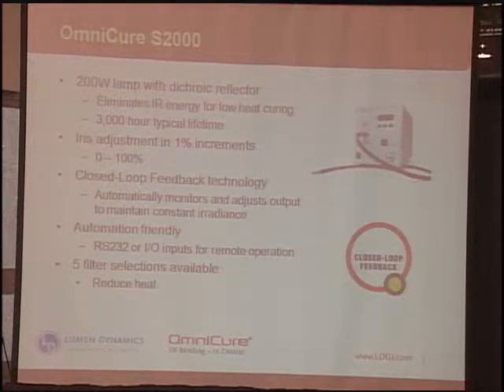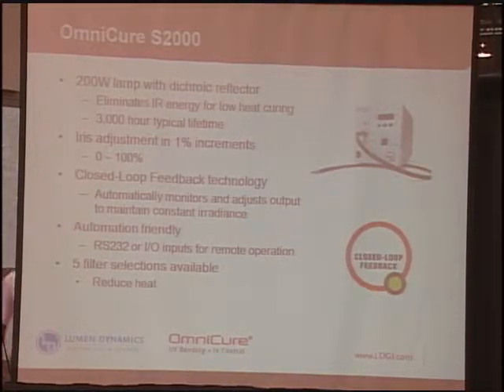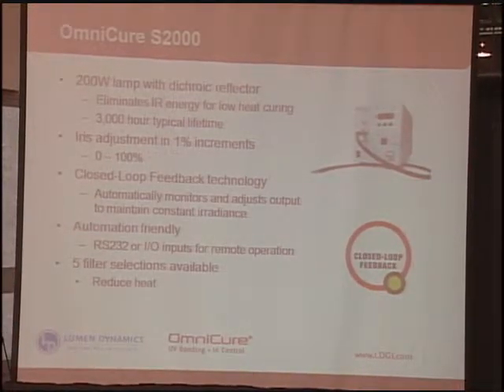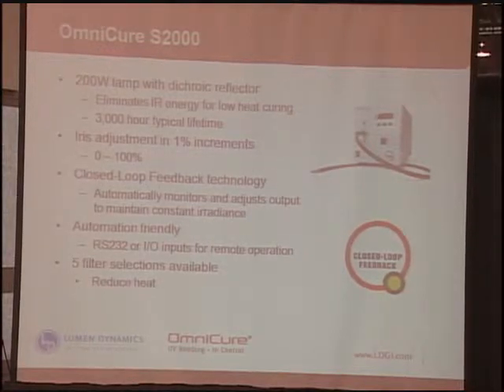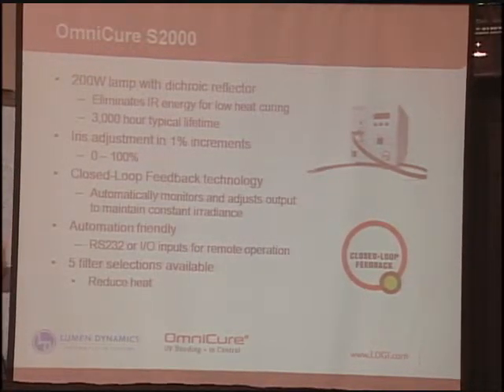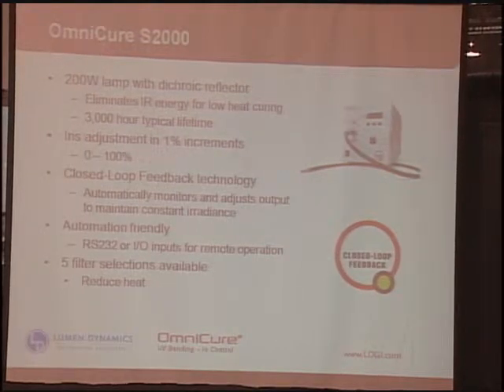One of the real unique features within the Omnicure 2000 is what we call closed loop feedback technology. With any arc lamp, it's going to degrade over time. So the closed loop feedback will automatically monitor the output from your system and then make any adjustments to the output in order to maintain a very steady irradiance level. That allows you to have a very repeatable process because you know you're always going to have a very repeatable irradiance coming from the system. The system is automation friendly, so it can be run through an automated system or it can be run manually.